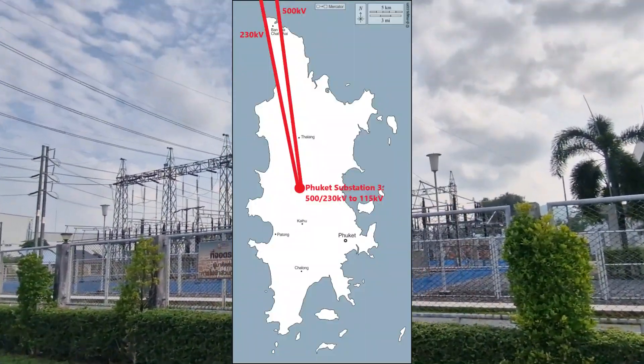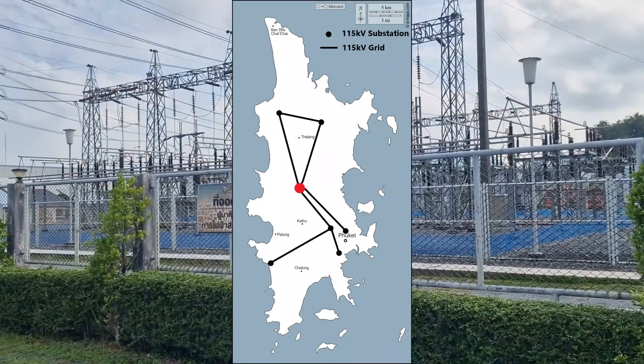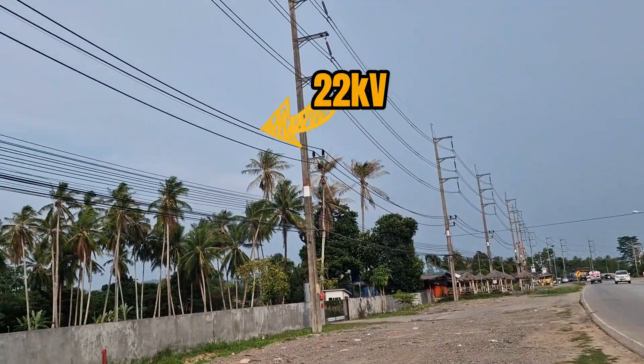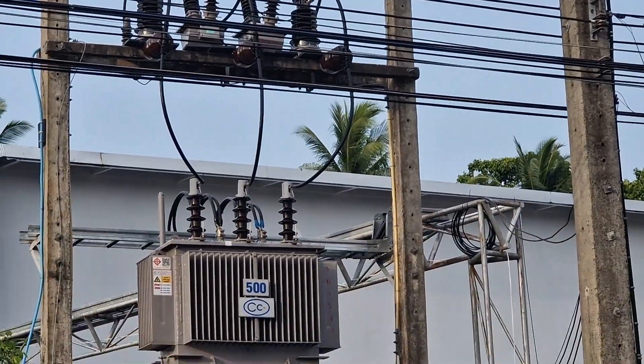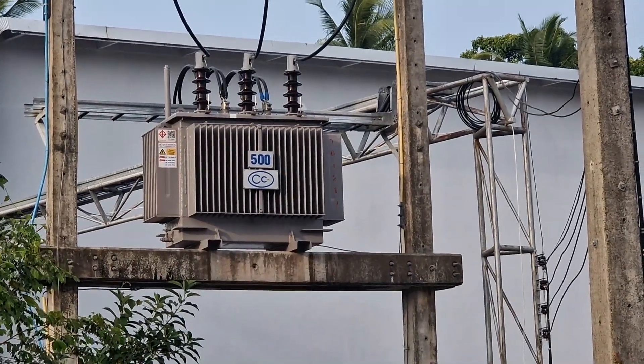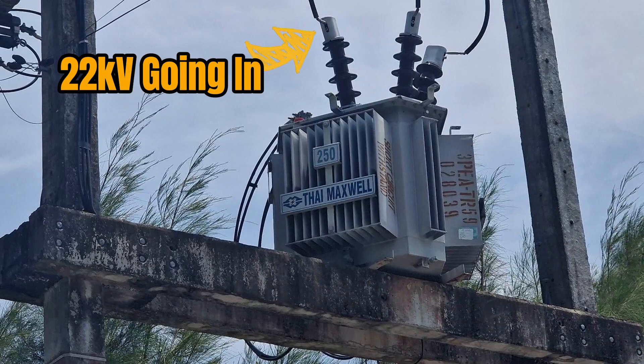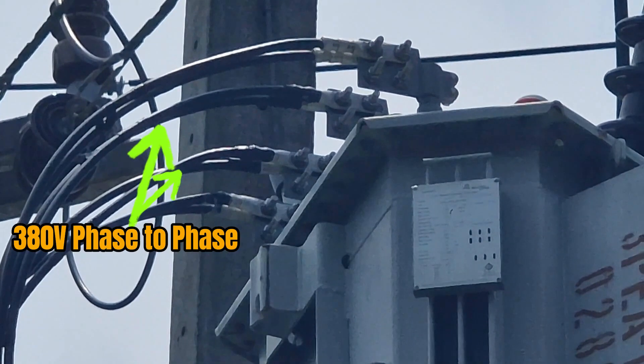So far we've figured out where the electricity comes from, how it gets from the mainland to Substation 3, and then to the various substations around the island on the 115kV grid. We also know that it then gets stepped down to 22 kilovolts for industry and local area distribution. But how do we get that sweet household-friendly 220 volts? That's where these little unstoppable iron-core-wielding, magnetic-field-inducing, voltage-whispering thunder boxes come in. This one's a 250kVA Thai Maxwell Electric pole-mounted transformer, a hermetically sealed oil-filled miracle. It takes 22kV buzz juice and outputs 220V phase-to-neutral or 380V phase-to-phase.